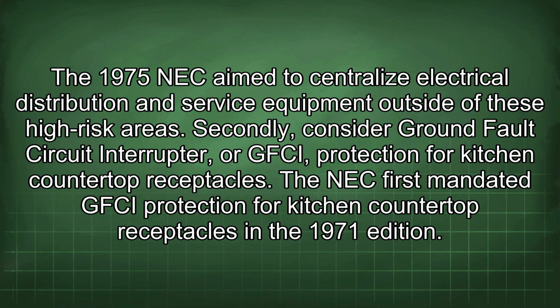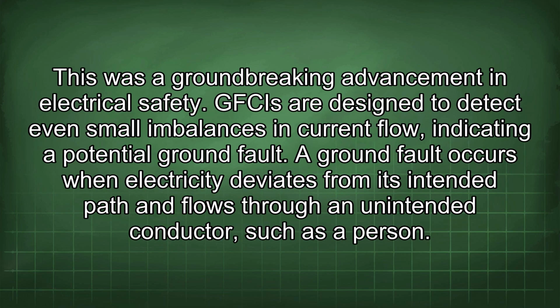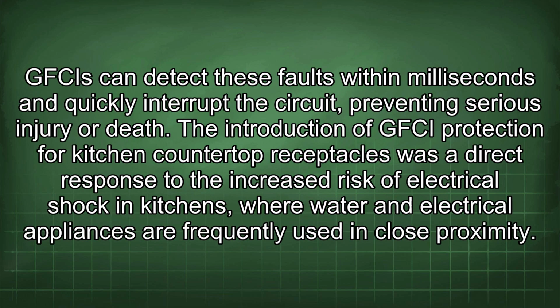The NEC first mandated GFCI protection for kitchen countertop receptacles in the 1971 edition. This was a groundbreaking advancement in electrical safety. GFCIs are designed to detect even small imbalances in current flow, indicating a potential ground fault. A ground fault occurs when electricity deviates from its intended path and flows through an unintended conductor, such as a person. GFCIs can detect these faults within milliseconds and quickly interrupt the circuit, preventing serious injury or death.